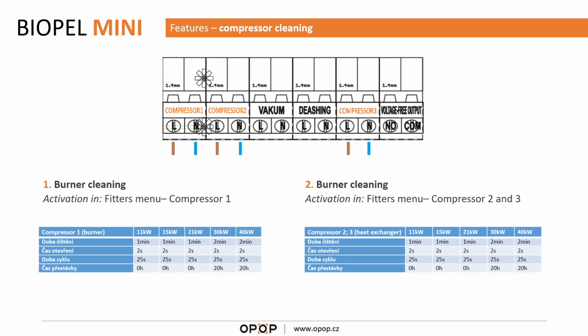Electrical connection and the setup is simple. Inside the control unit there are 3 outputs named compressor 1, compressor 2 and compressor 3. Compressor 1 is dedicated for the burner cleaning, and compressor 2 and compressor 3 are dedicated for heat exchanger cleaning. Here I have a mistake. This is not burner cleaning, this is the heat exchanger cleaning.